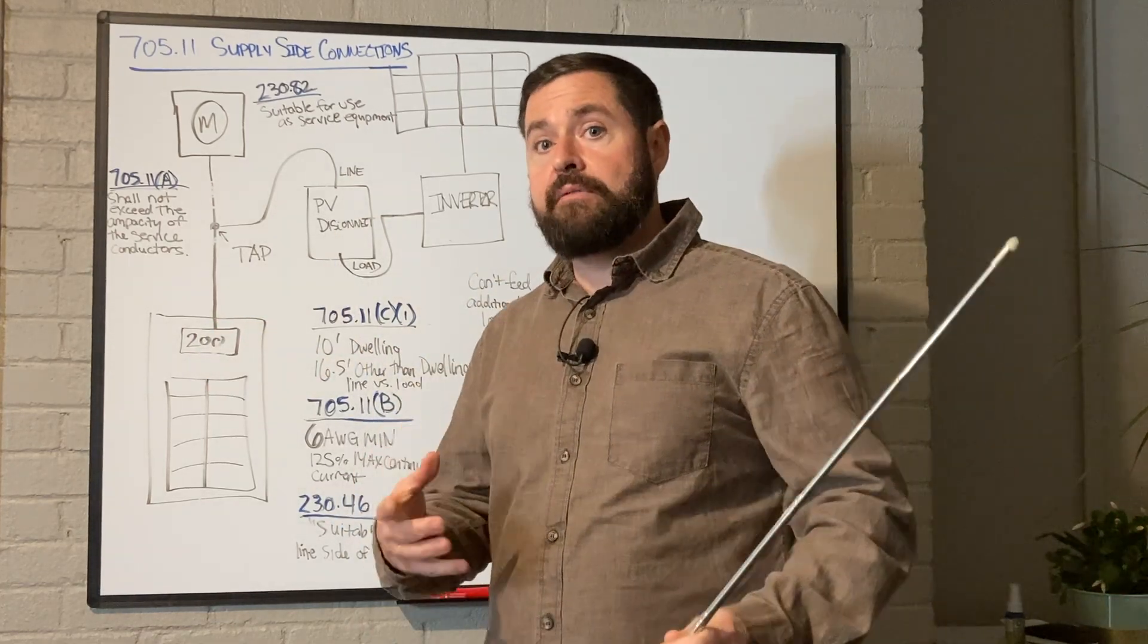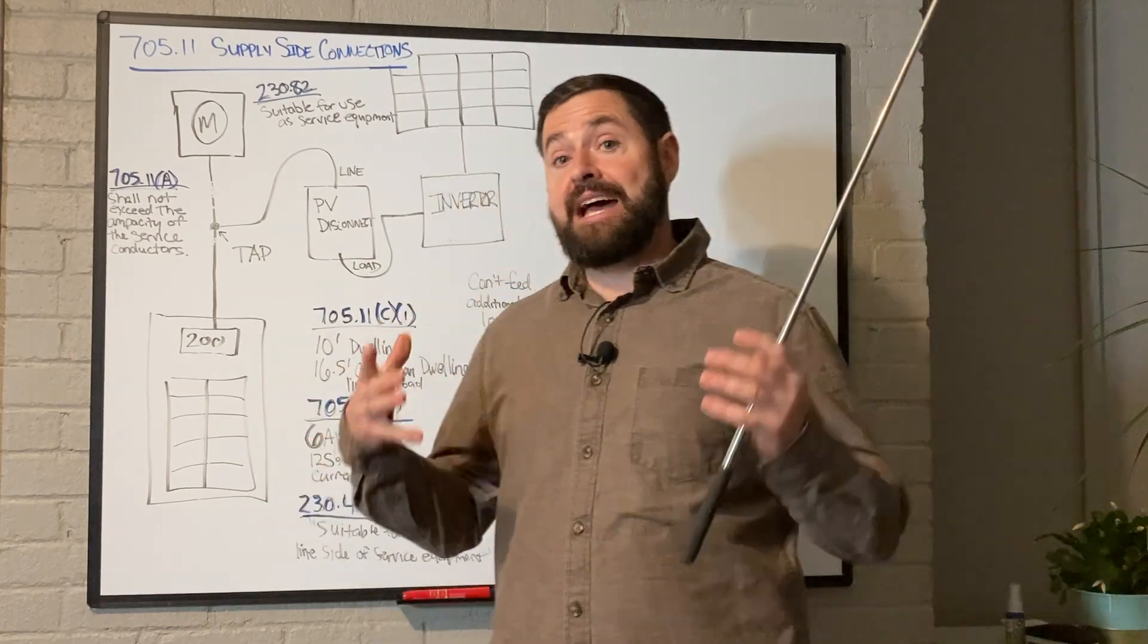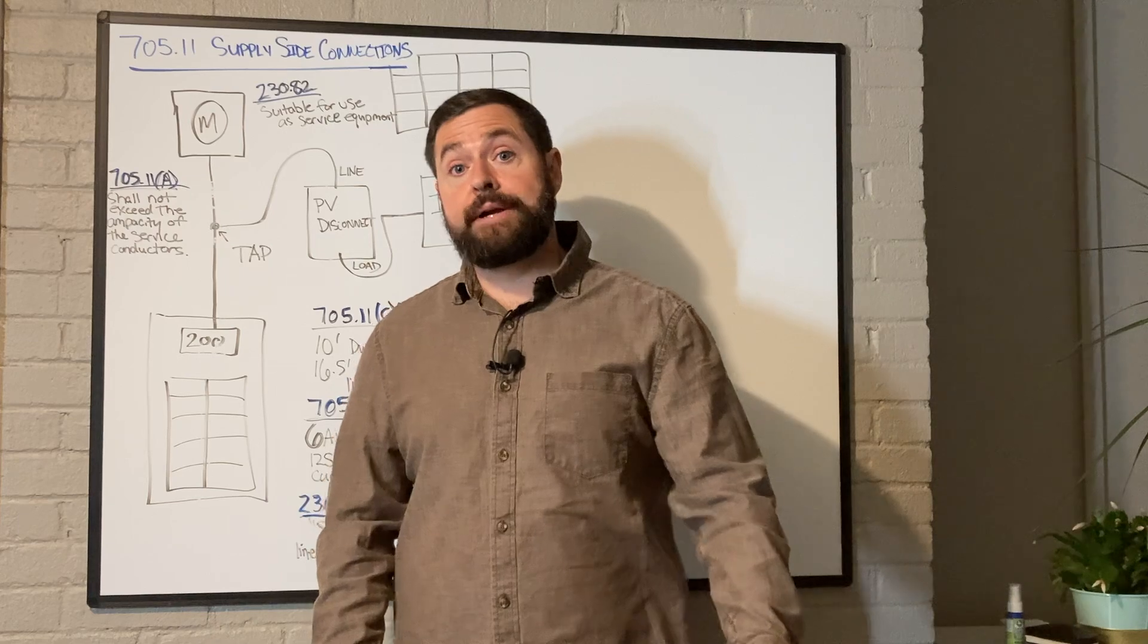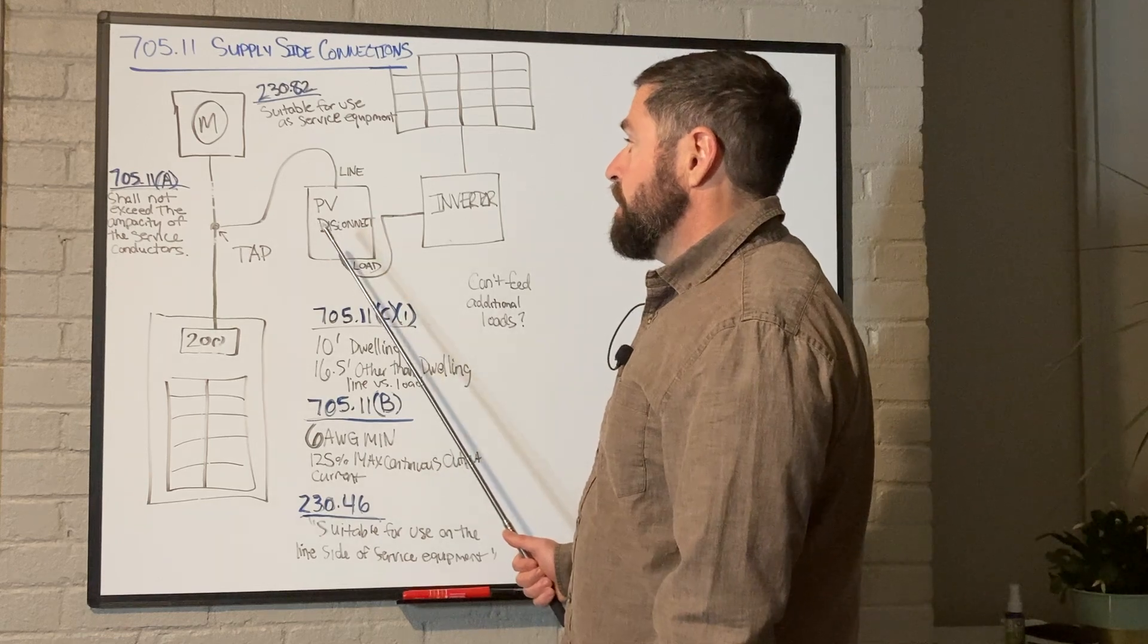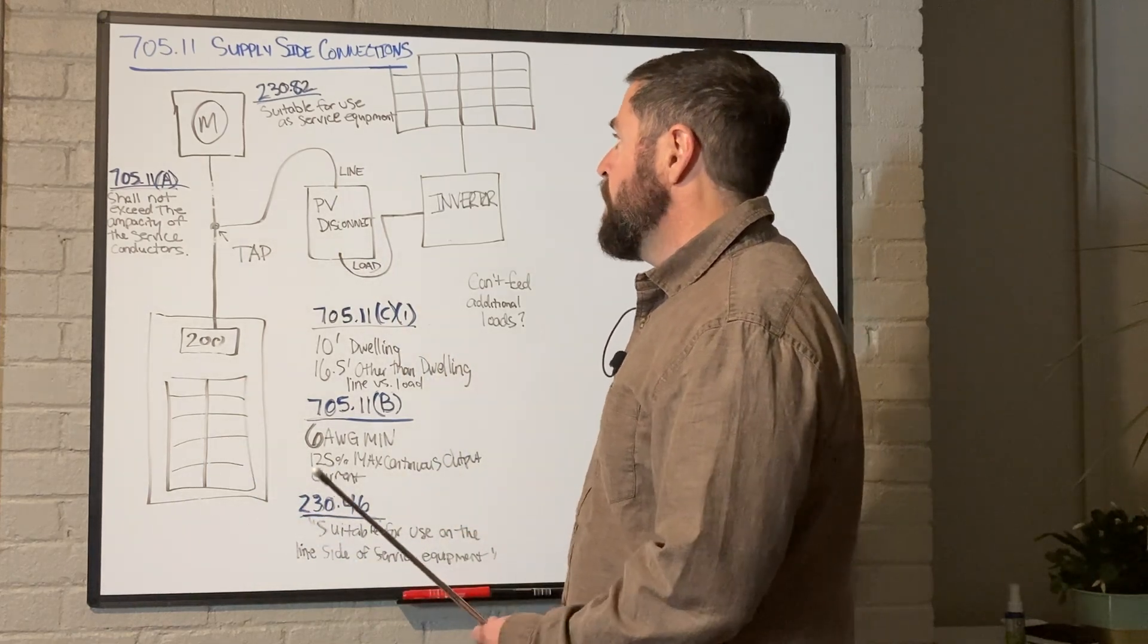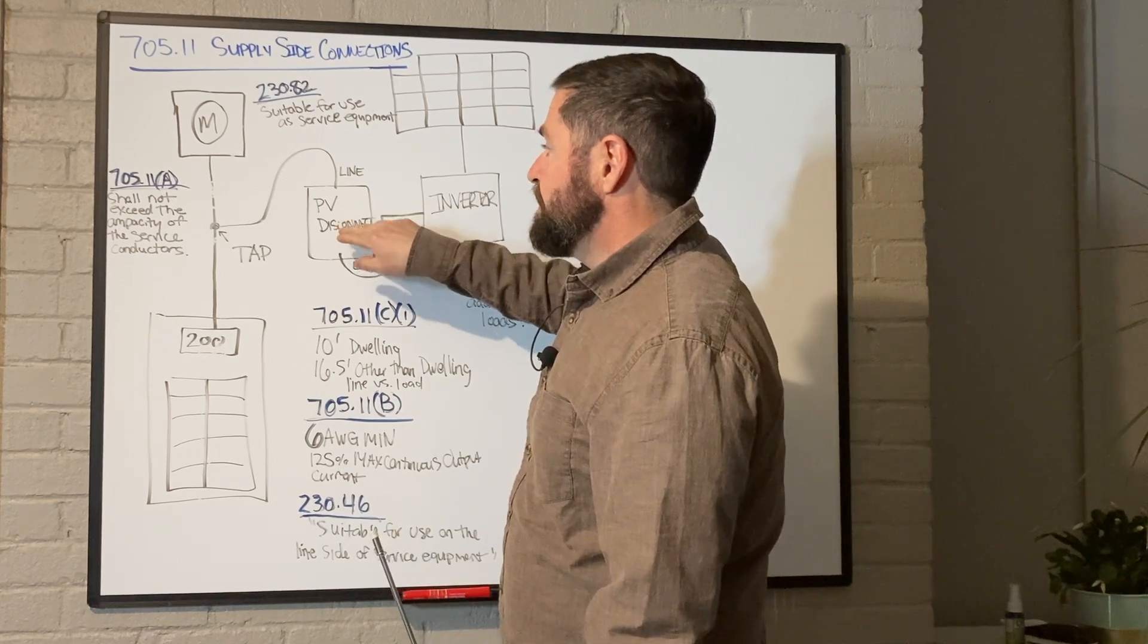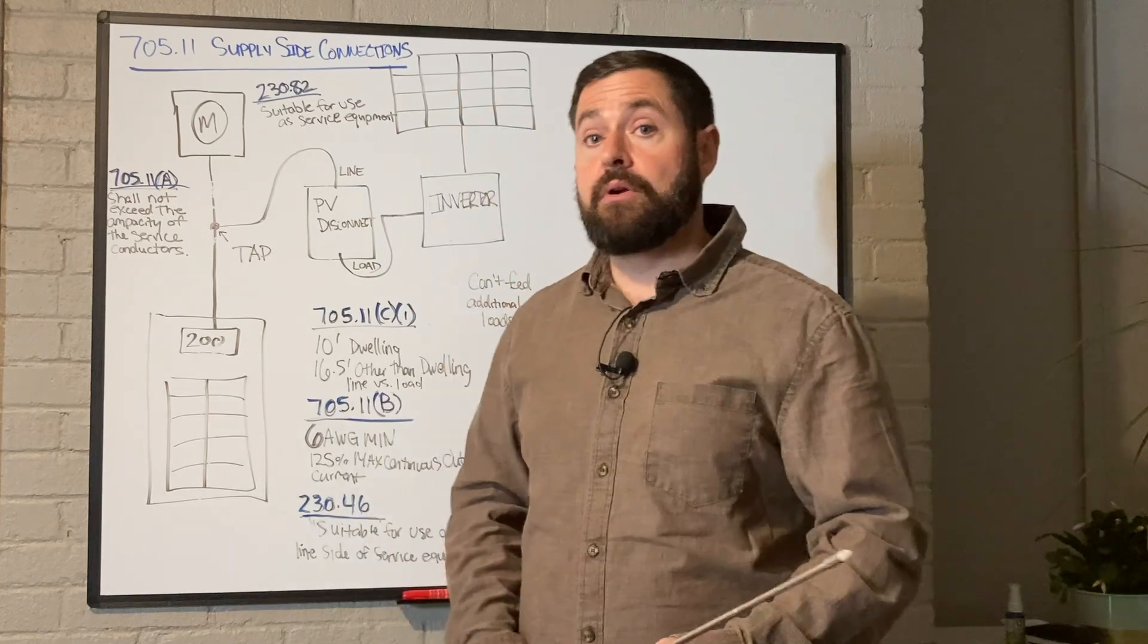Now what you never want to do is have neutral current running on your equipment ground. That's what's called objectionable current. And so that would happen if, say, you bonded your ground and neutral in the disconnect and then continued to run all four to their respective locations in the main service panel. And during normal operation, you would have a parallel path for your ground and neutrals, and so you'd be sending neutral current back on your equipment ground conductor, which you should never do. That can create a dangerous situation for an unassuming electrician.